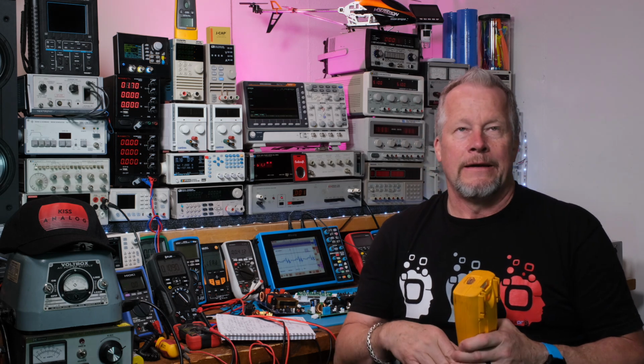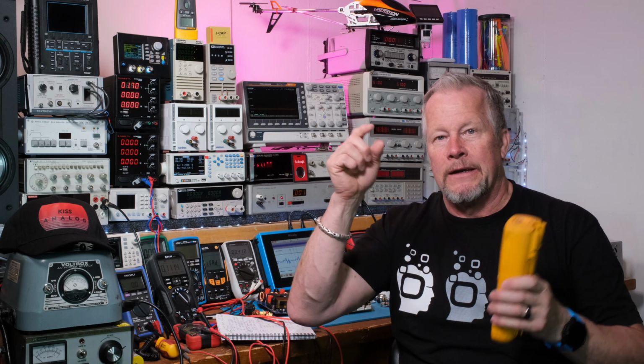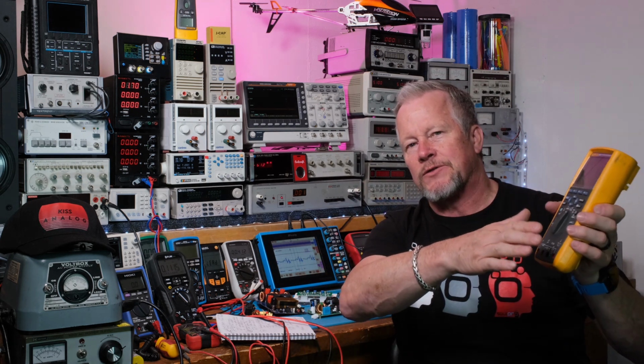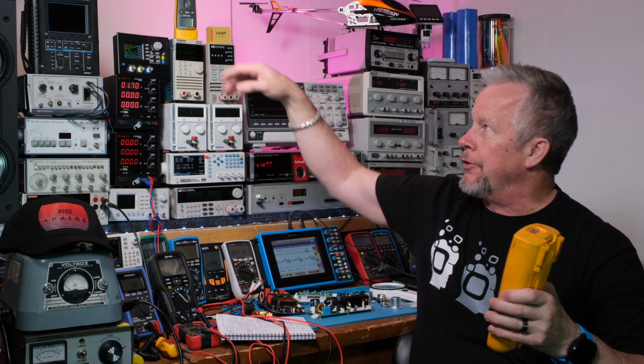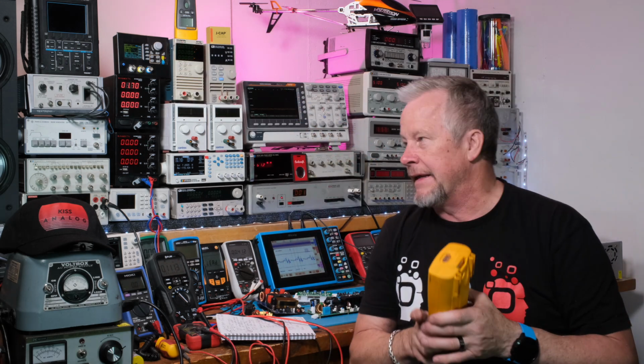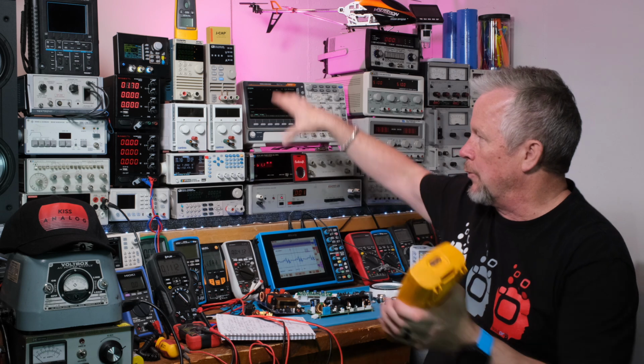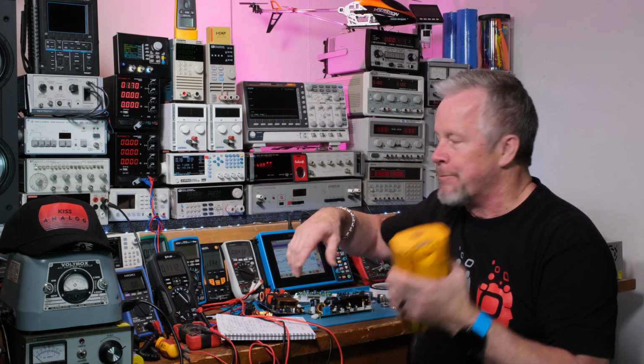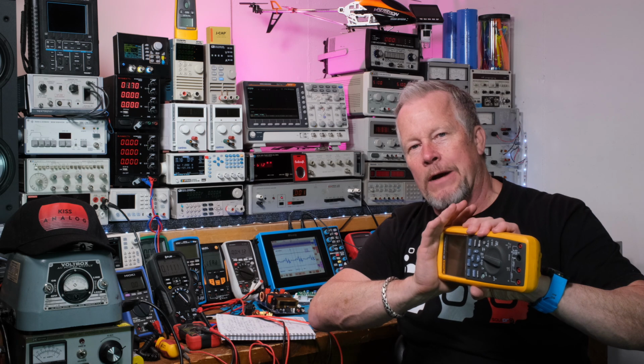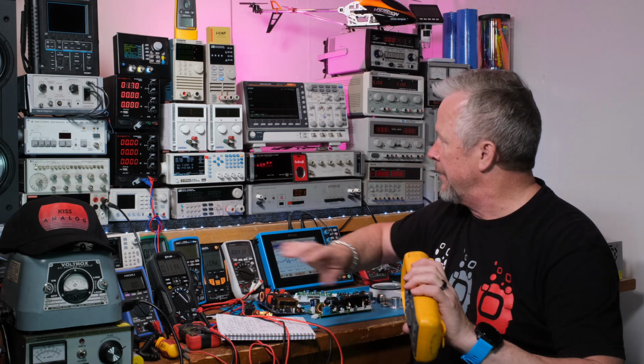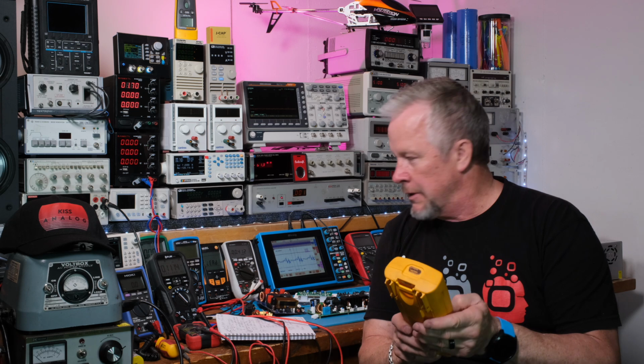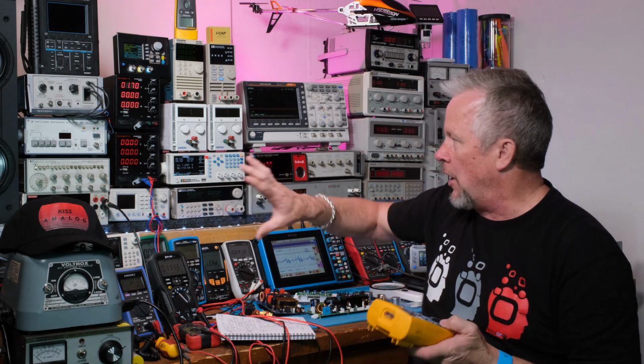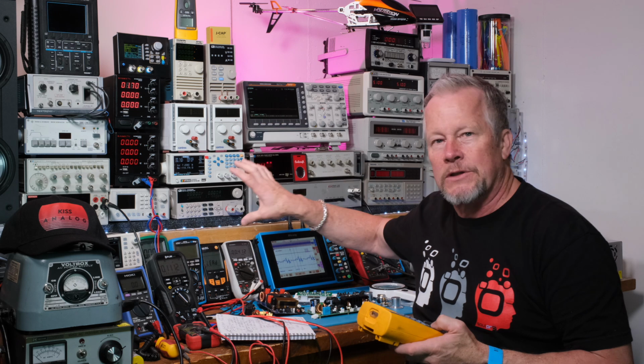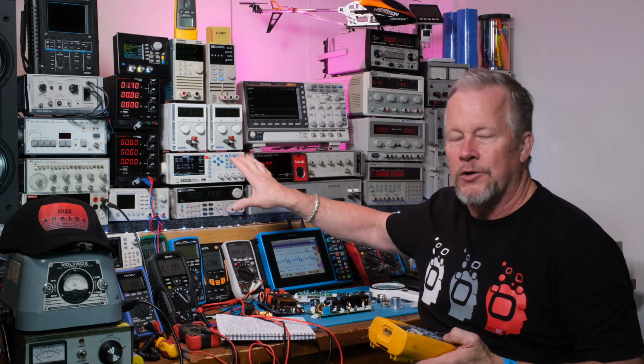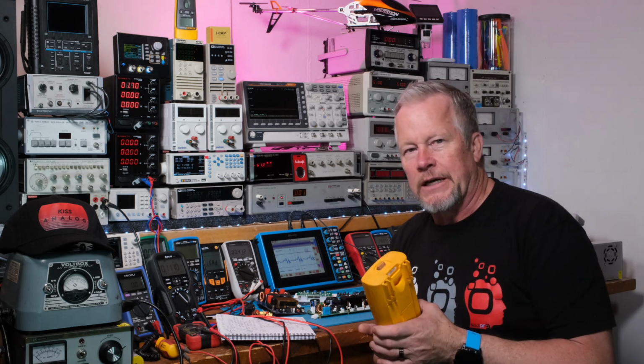Cat 3, I've gone over this a bunch of times, but Cat 3 is the wires from the service entrance where the power comes into the building to the panels, okay? And then Cat 2, Cat 1, that's where we work. That's this stuff. When I see reviewers, oh gosh, I got another rant topic. When I see reviewers go, gosh, I want to trust this cheap meter to work around high voltage. This is not high voltage. This is 120 volts here in the US, your 240 volts. That's not considered high voltage, guys.